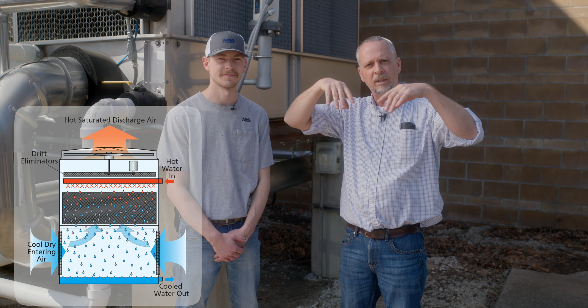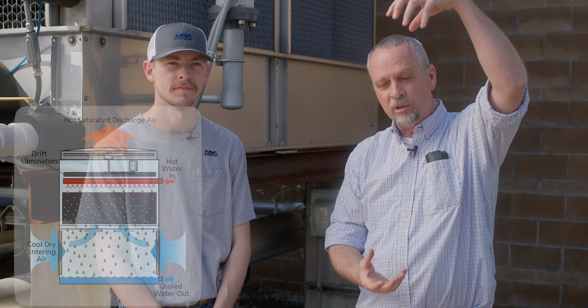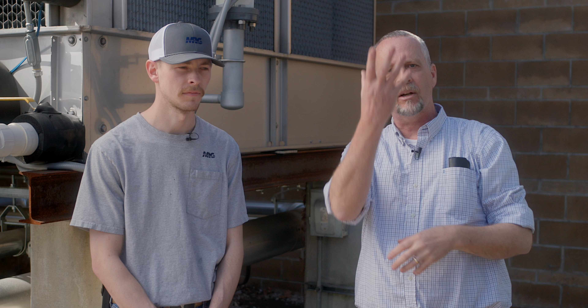So a counterflow tower, like you see behind us, is pulling air from all four sides of the tower from the bottom and flowing it up. So in other words, we're countering the flow of the water. The air is counter to the water. The water's coming down and the air is going straight up.